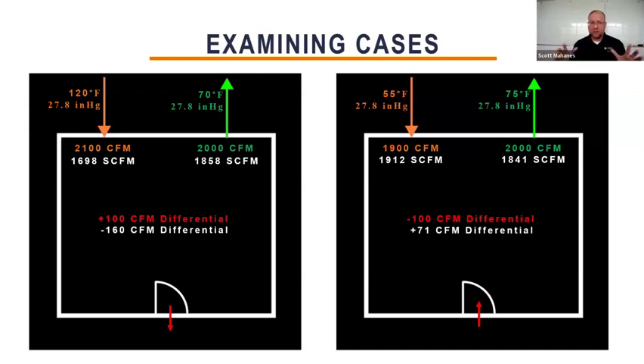Now, this is an extreme example, but 100 CFM volumetric difference is very different from a minus 160 mass flow difference. And a minus 100 CFM volumetric flow difference is very different from 71 positive difference. And in reality, these rooms are going to drive into different pressurizations, not because there's something wrong with calibration of the volume. It's because the volume alone isn't the right value to differentiate what kind of pressure you're going to have. It's on mass. And I promise you, if it's true for a room pressure, the same thing's going to happen with a building pressure differential.